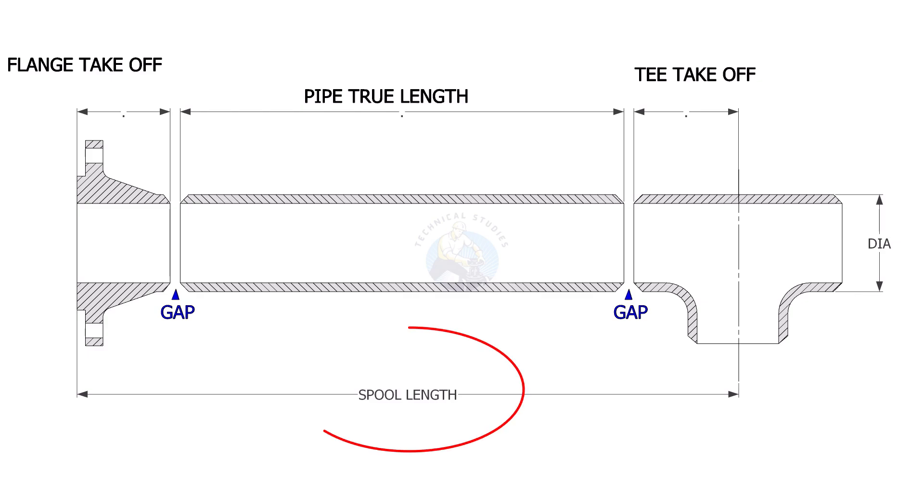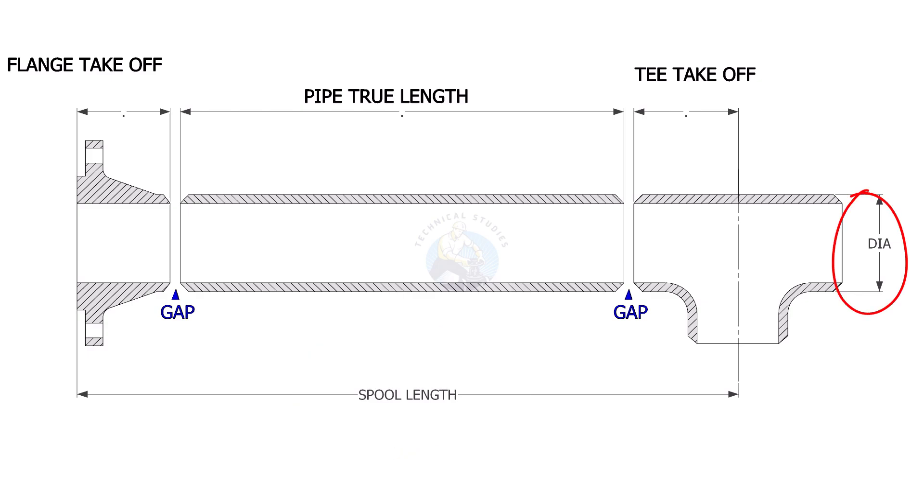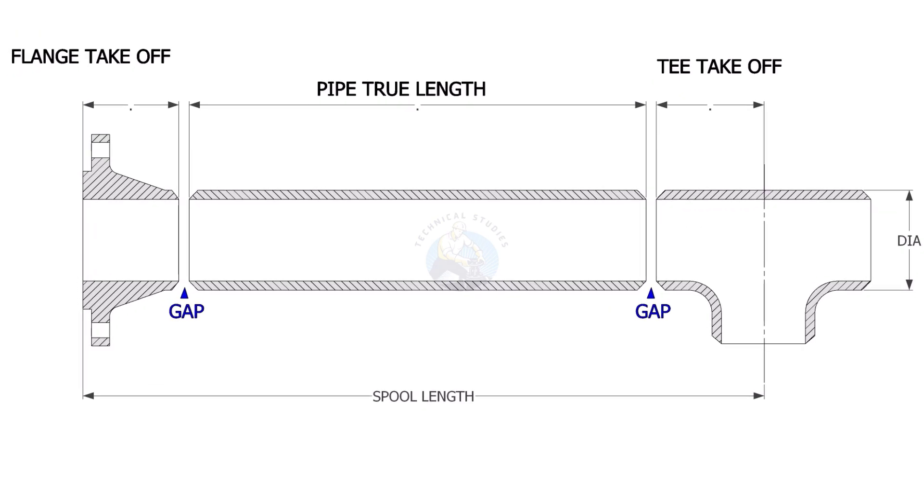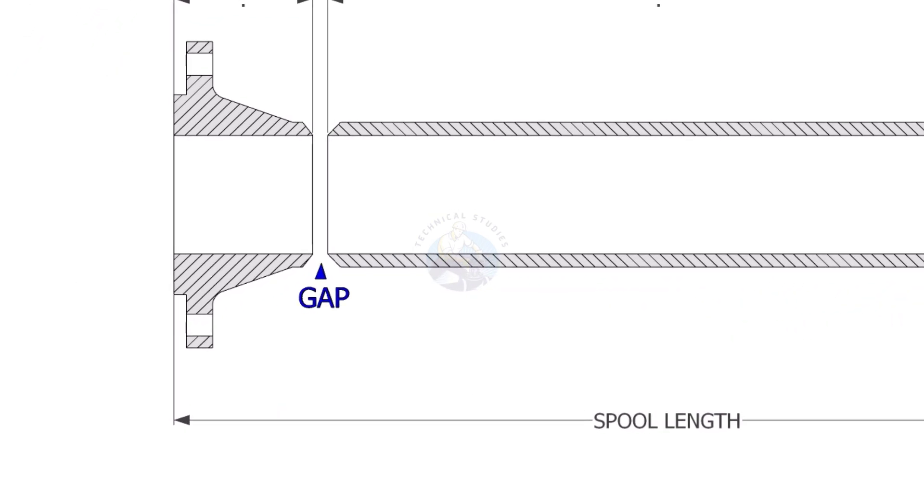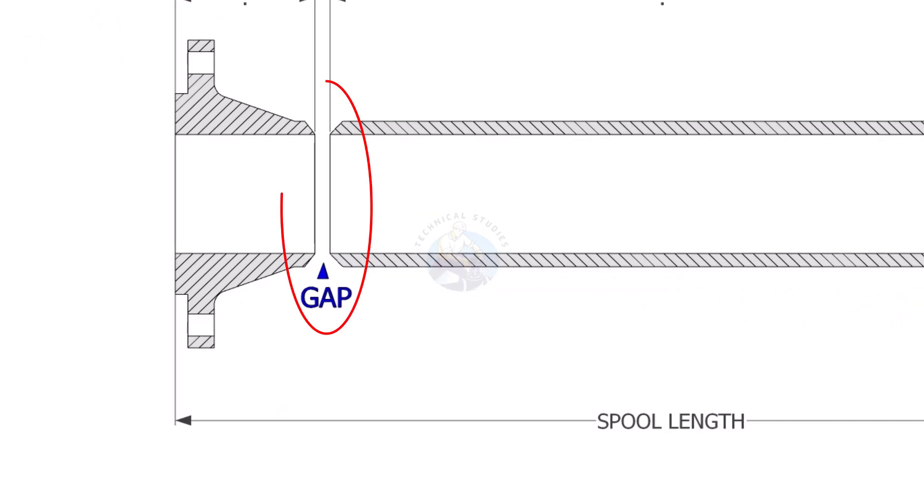To determine the pipe length, we need to know the spool length, spool size, takeoff length of the flange and the T, and the flange rating. Usually, the gap between the joints is three millimeters.